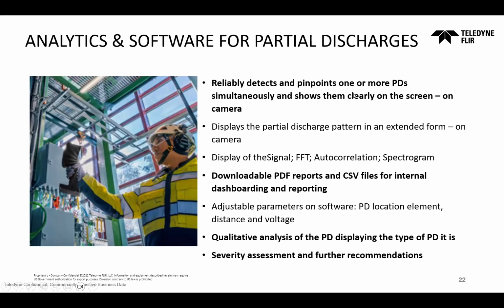Okay, analytics and software in partial discharges. Find the PDs, as I said, it's the same as with leak detection. So it finds individually and simultaneously different partial discharges on the screen. It shows the partial discharge pattern. You need to be a big expert in order to recognize the patterns and determine from the pattern what kind of partial discharge it is.